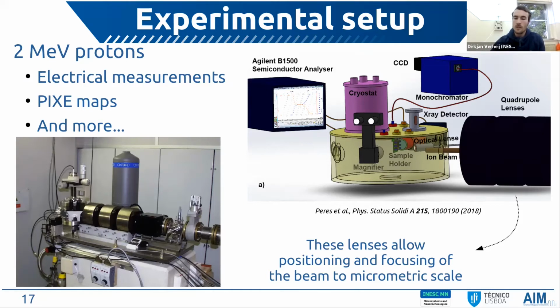And we also can position the beam with this same precision. So the chamber, furthermore, allows for a series of detectors to be included. So we have an X-ray detector, optical lenses, and electrical wires can be connected. So this allows for simultaneous electrical measurements and proton-induced X-ray measurements during the irradiation. So from this, we can actually extract a lot of information.